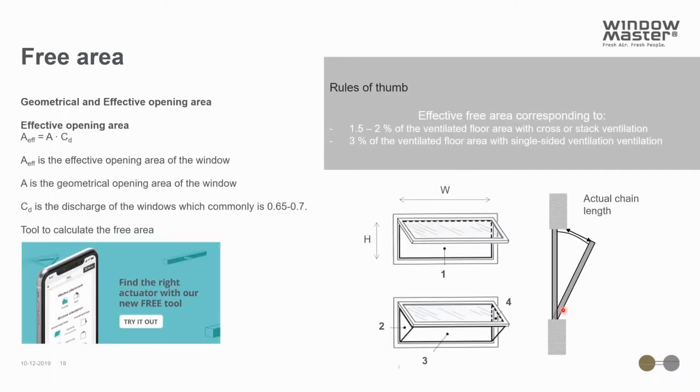The free area of an operable window can sometimes be tricky to define. It's not always simple geometry, but generally it's based on of course the geometrical opening area of a window multiplied by the discharge coefficient of a window. And for a standard top hung window, the discharge coefficient is typically around 0.65 to 0.7. This discharge coefficient will vary a little bit based on the window type.